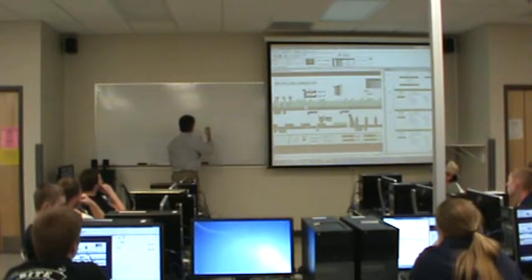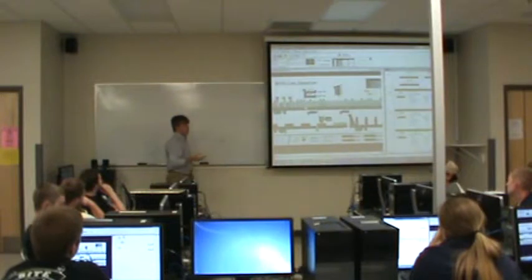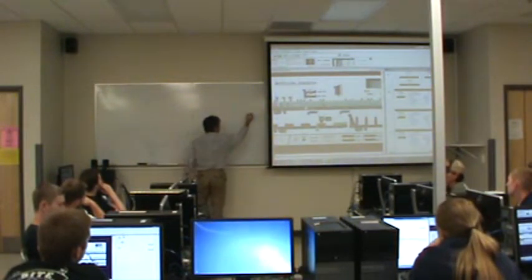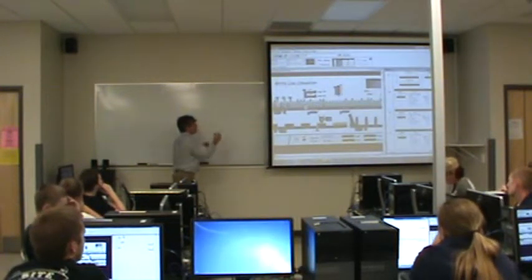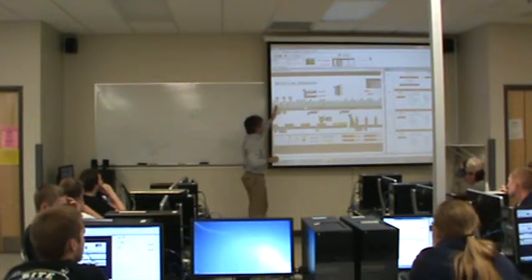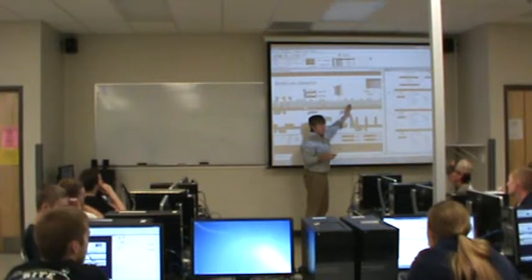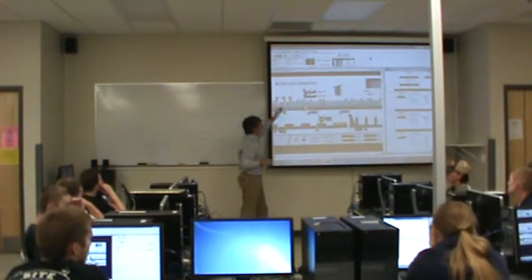Okay. And as you continue, each time the conveyor indexes, you just shift all these bits. That's what the bit shift instruction does. It just takes all the bits and moves them down one. Now the bit that's on the end just gets thrown away sometimes. The way I set it up, it actually goes into another location because if you think about it, there's more than 16 bottles along the way that I have to deal with. But there's less than 32, so I only needed 2 words of data. And that way I could keep track of broken bottles as they move.